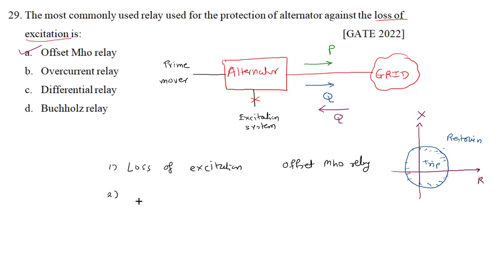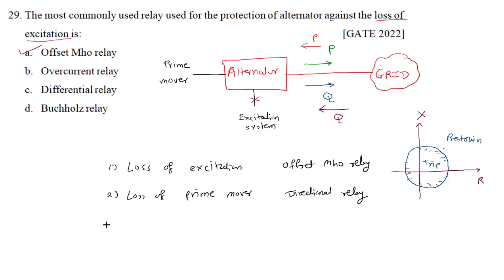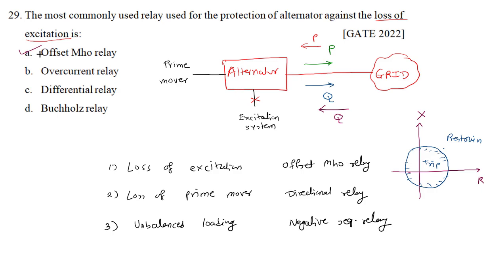Sometimes there might be a loss of prime mover. In that case, the alternator will still supply reactive power, but will take active power from the grid — a reversal of active power flow — and we use a directional relay to detect loss of prime mover. For unbalanced loading, there will be flow of negative sequence current, and we use a negative sequence relay to detect that condition. The correct answer is option A — offset mho relay.